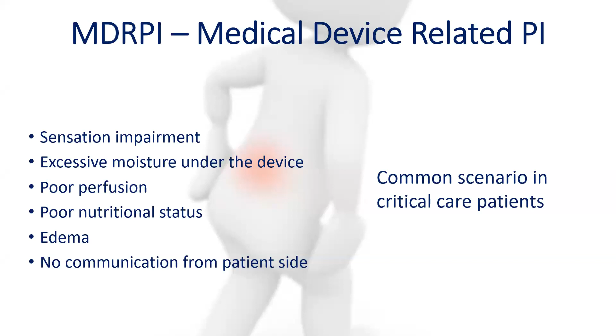Another reason why this happens, besides these contributing factors, is the wrong size. Sorry, it's wrong size, not wrong side. It could be the side as well, because if we apply it improperly, of course, it would be contributing or it would aggravate the situation. But in this case, wrong size of the device. If we put on a too small medical device, for instance, speaking about the BiPAP, it will probably cause more pressure than if applied properly. If we put on one too big, eventually we will need to tie it tighter to try to not have leaks and to have the pressure settings that we want, that are recommended and prescribed. So it will, of course, have more predisposition to develop pressure injuries as well.